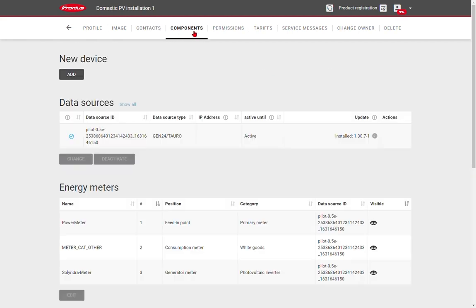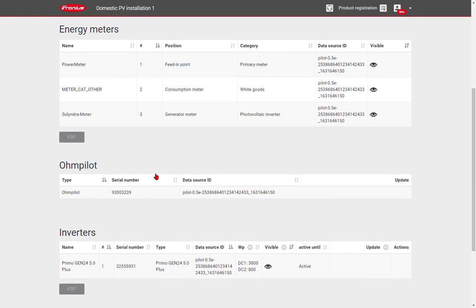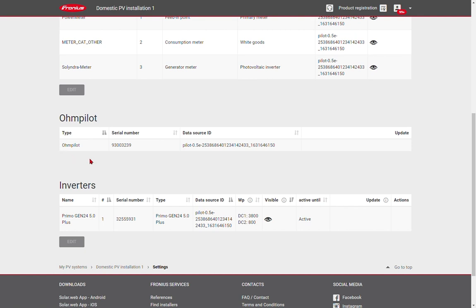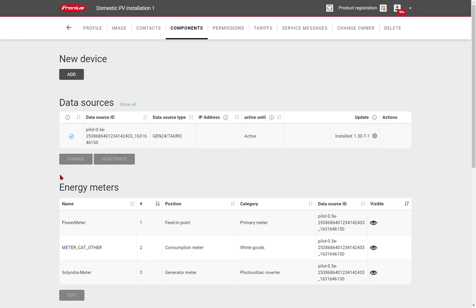Under components, here we see a list of all devices that are connected to this system in SolarWeb. First of all, we see our data sources. These are our data manager cards or the pilot boards within a Gen24 or Tauro inverter. We see our energy meters. We'll have our primary meter, which is in the feed-in point. This is the one measuring the import and export energy for the grid. We have our consumption or generation meters as well, if we're measuring additional devices on the site. We have our Ohmpilot for hot water. We might see an EV charger, the Watt pilot listed here as well, and also a list of any connected inverters. Devices that can be updated will be shown with a checkbox. You can click on that checkbox to run the latest software update. We can see here that the current system is up to date with the latest firmware.